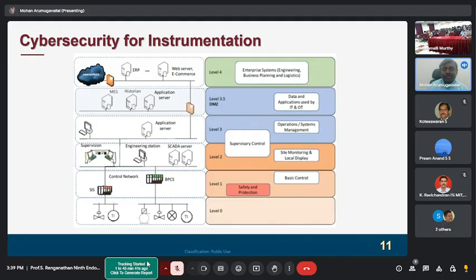So it's all coming at 4 to 20 milliampere, so there is not much information available for the control systems. But with digitalization, there are hart-enabled devices wherein the diagnostic information and additional parameters can be transferred, and you can do remote calibration for the devices.